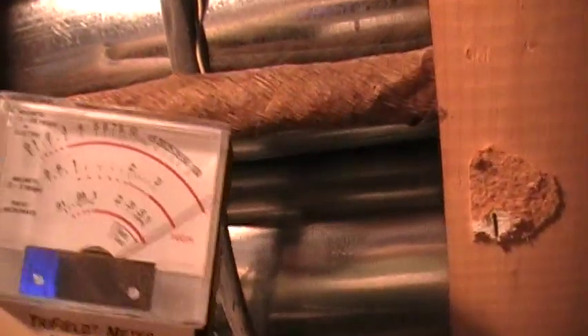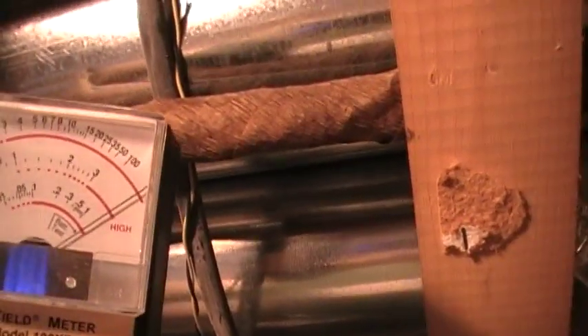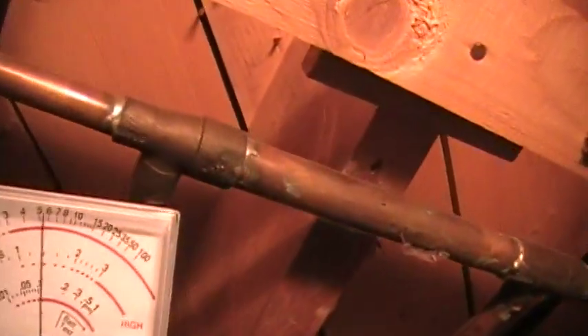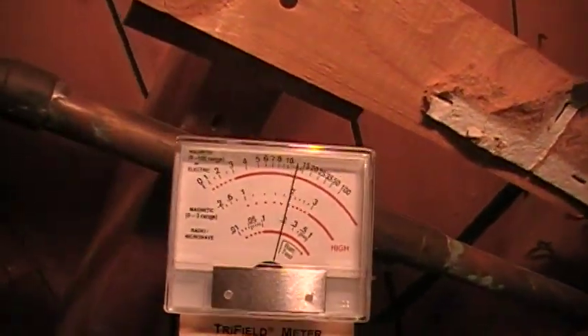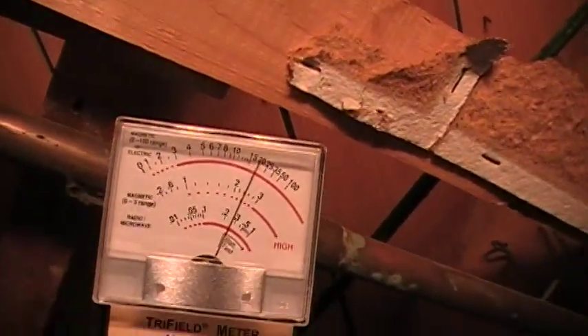There's the water main a little bit further along. We'll go look at some of the hydronic piping. That's showing around 5 or 6, spiking up around 10, 15. Basically all of the pipes in the basement are energized with this magnetic field.